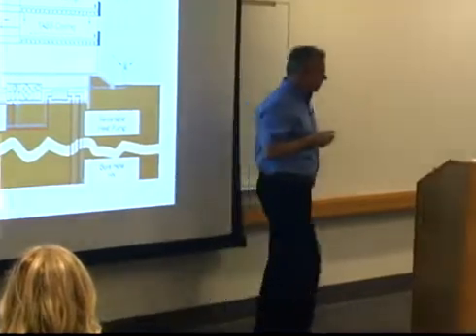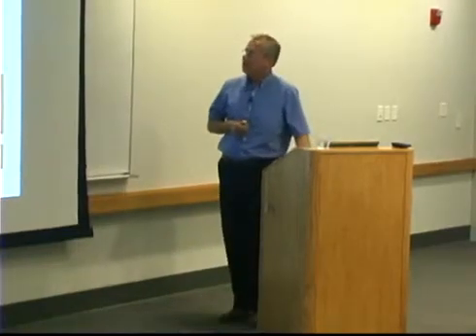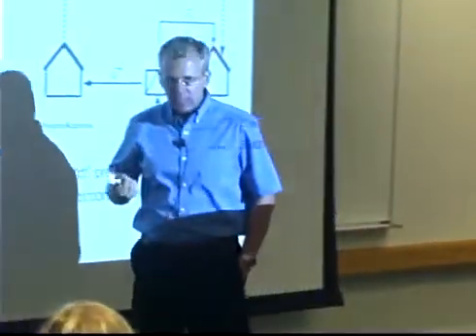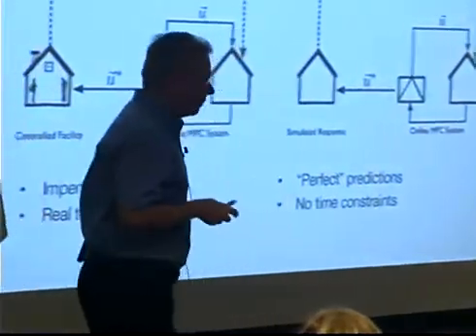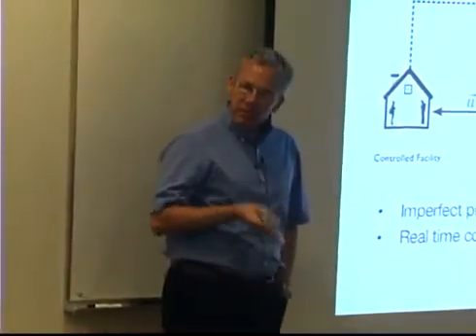So we took a building like this and we asked, okay, if that's the best we can do, how should we operate it? The paradigm for operating such a building that we adopted is one where we ask for the best possible operation of a building through a reasonable time period, and the reasonable time period is 1 day or several days in a row. The approach we have adopted is known as model predictive control. Model predictive control is an established control paradigm within the industrial engineering and chemical and pharmaceutical engineering industries. But in buildings, it's a relatively recent development.